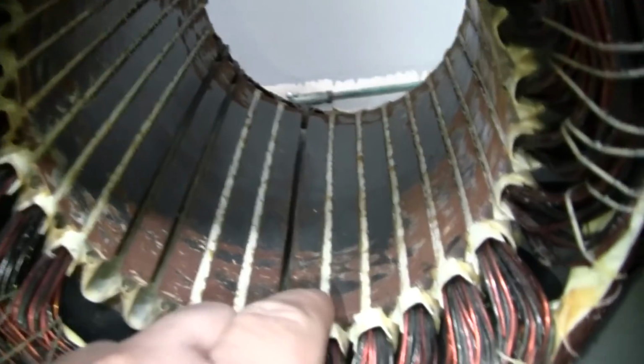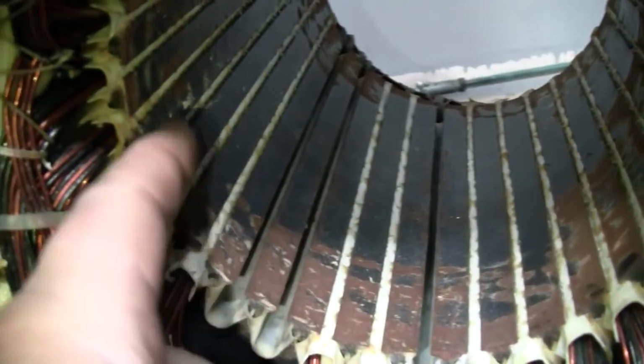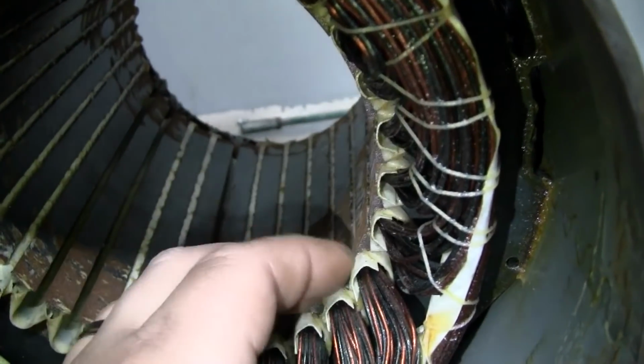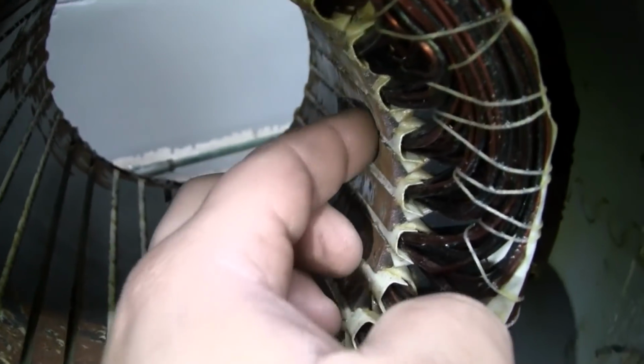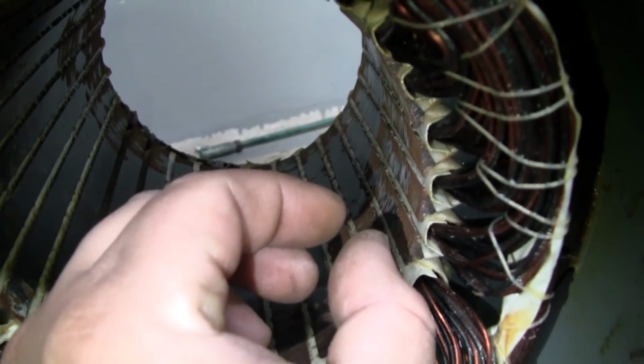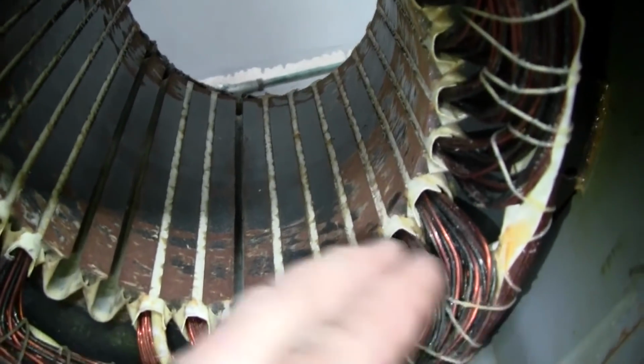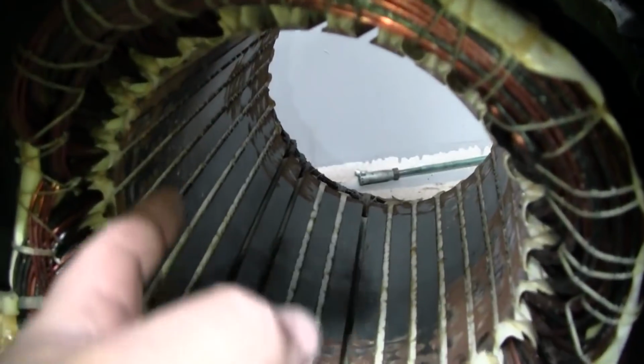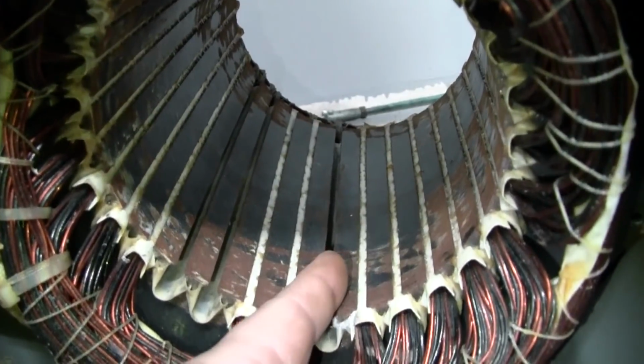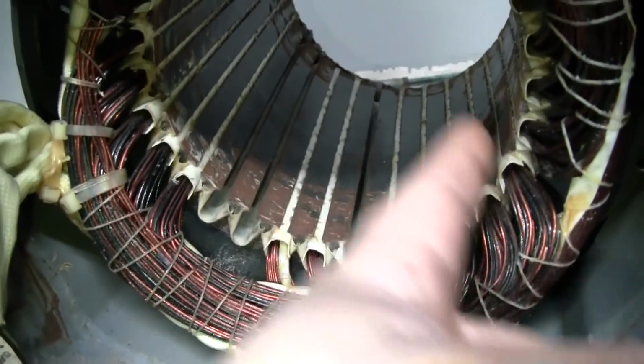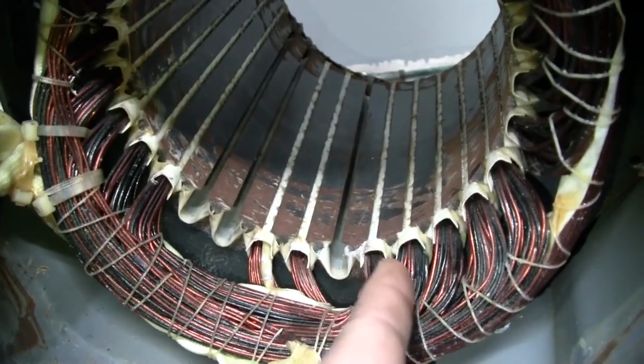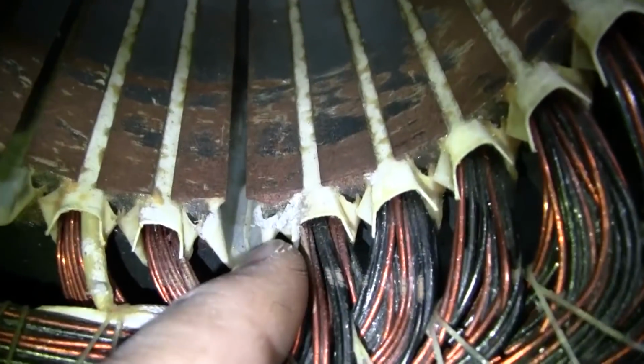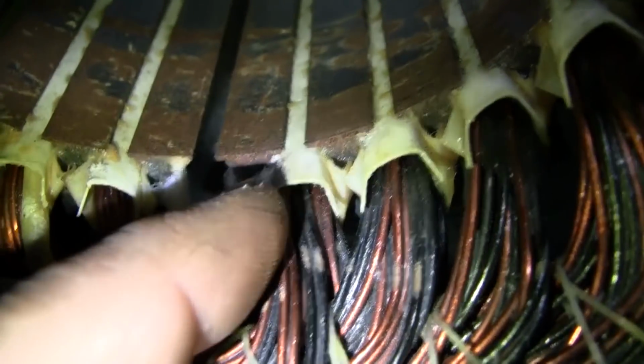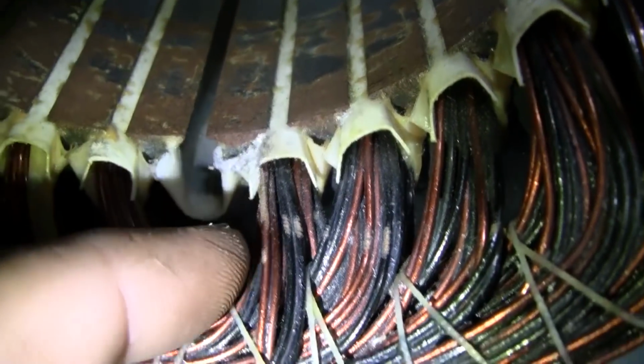Because of these scratches we see in here, I think that the finish, the resin they used to seal this originally, there must have been some drops or imperfections here that would not allow the rotor to clear. There's a very small gap between the outside of the rotor and the inside of the stator here. So I think they went in here with a drum sander to try to sand away those high spots, and in doing so they got sloppy going around and around, and they rammed right into the windings here, based on just how the paper that lines the slots is abraded there, and the windings.